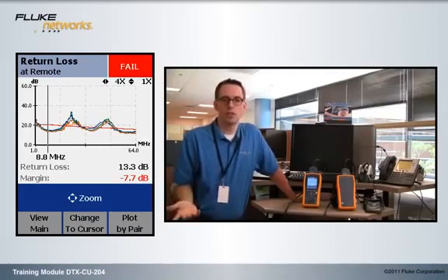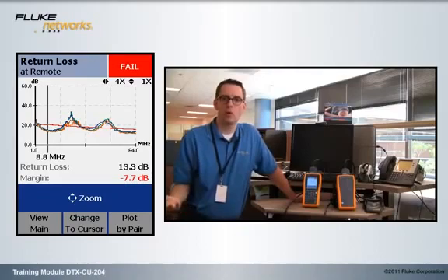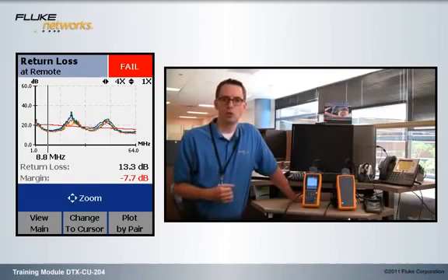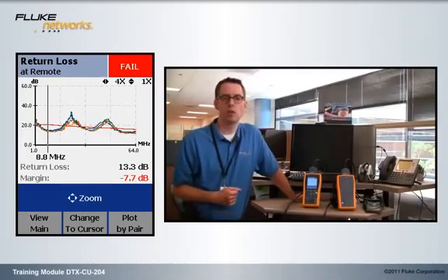And at this stage in the game, there's no point in going on. That cable's got to come out. It's probably in conduit and you've got to find out how to dry out that conduit. If it's external, then you'd be needing to look at an OSP cable.